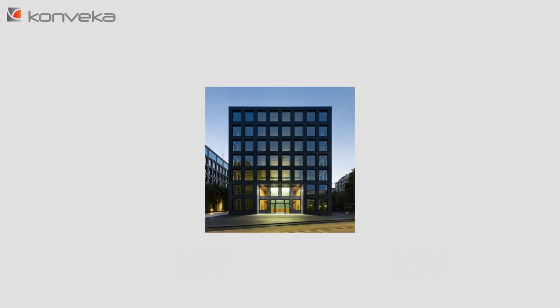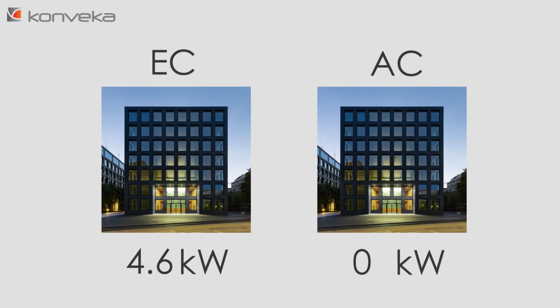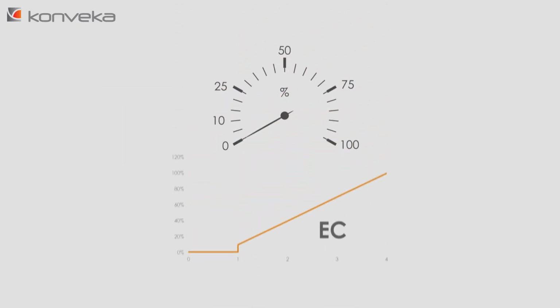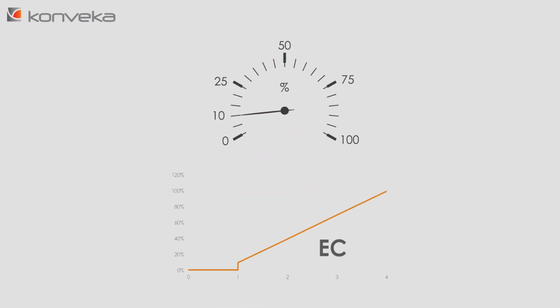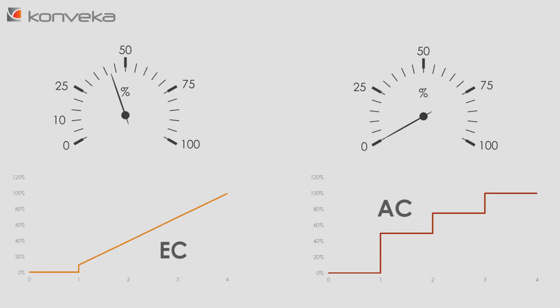For an average administrative building, approximately 4.6 kilowatts of power consumption will be sufficient in the case of an EC motor, whereas fans with AC-type motors will require 30 kilowatts of power. EC motors start at 10% of their maximum rotation speed, while the speed is controlled smoothly without jumps. As a result, their operation is almost imperceptible. AC motors cannot rotate slower than at 50% of their maximum rotation speed. Their speed is controlled by using a frog jumping algorithm. This reduces their service life and increases the noise level.